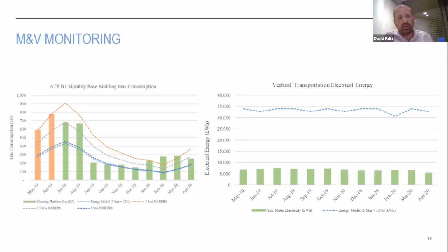The gas consumption, we were a bit over where we wanted to be. We'd modeled this building at about 5.4 to 5.5 stars, and we were over that, but still in a good 5.5-star range at first. We managed to get the boilers down significantly, but then because of dehumidification in the summer months, we saw gas usage increasing above where we wanted it to be. So it's certainly a learning curve in tuning the building, especially around gas and dehumidification around chill beams. There's been some good learnings there.